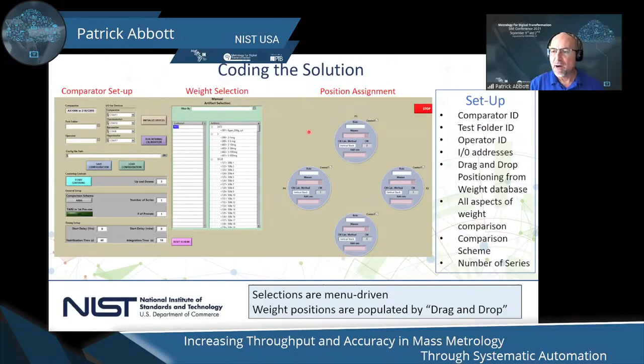So looking at the other application for comparator setup, it allows us to choose a given instrument. We have 11 different comparators, and we can put in a test folder for that particular calibration if it's a customer calibration, put in the operator's name, and save the configuration of everything. And again, all of the things that pertain to running a given calibration: the number of series you want to run, pre-runs, start delays, etc. And again, we have to tell the comparator which artifacts actually to use, and the database helps us do that. When we choose a particular customer, all of the artifacts that we have for that customer show up, and we can populate the individual positions by just dragging and dropping onto these carousels. So this was a very nice programming feature, the drag and drop scheme that we have.